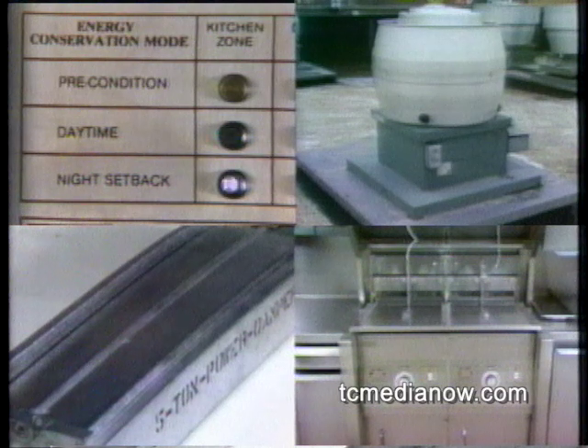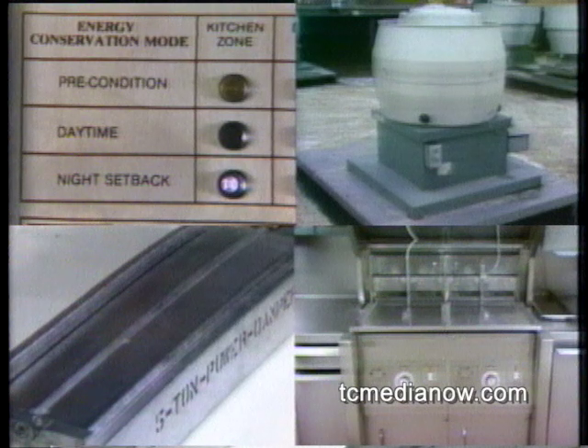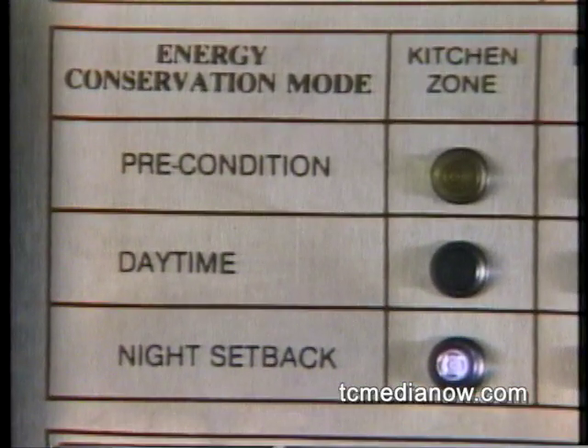The night setback mode is for periods when the store is unoccupied. It turns air conditioning systems completely off in summer. In winter, it maintains a minimum temperature of 50 degrees Fahrenheit. During night setback periods, no power is supplied to cooking equipment. All exhaust fans are off and HVAC dampers are closed.